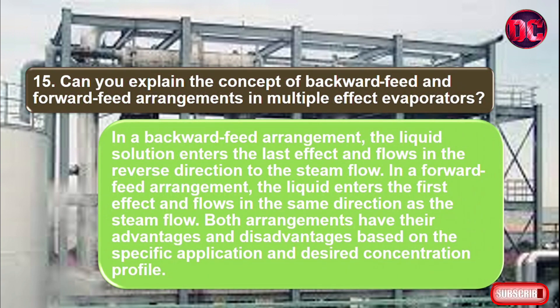Can you explain the concept of backward feed and forward feed arrangements in multiple effect evaporators? In a backward feed arrangement, the liquid solution enters the last effect and flows in the reverse direction to the steam flow. In a forward feed arrangement, the liquid enters the first effect and flows in the same direction as the steam flow. Both arrangements have their advantages and disadvantages based on the specific application and desired concentration profile.